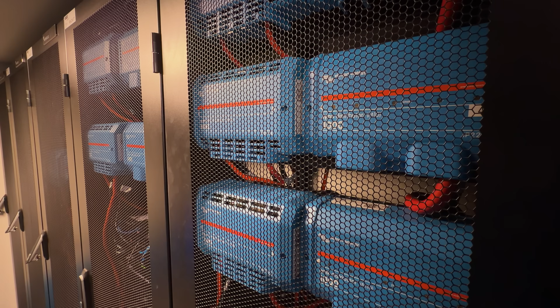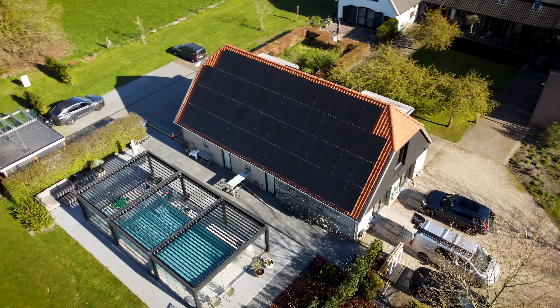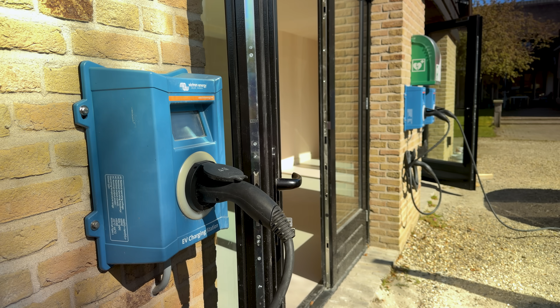But keeping your own data center online next to your house with no team of engineers on site is a serious undertaking. The answer was to build a system with so much redundancy that the risk of going dark became almost impossible. The property itself is substantial: 2 houses, an office, the data centre, a swimming pool, and at any given time up to 5 electric vehicles on charge. On a typical day, they're getting through around 600 kilowatt hours. There's a baseline of roughly 20 kilowatts, so we're always doing 20 kilowatts, just the data center, keeping the data center running and the cooling running. During high workloads, it increases to, let's say, 25 kilowatts.